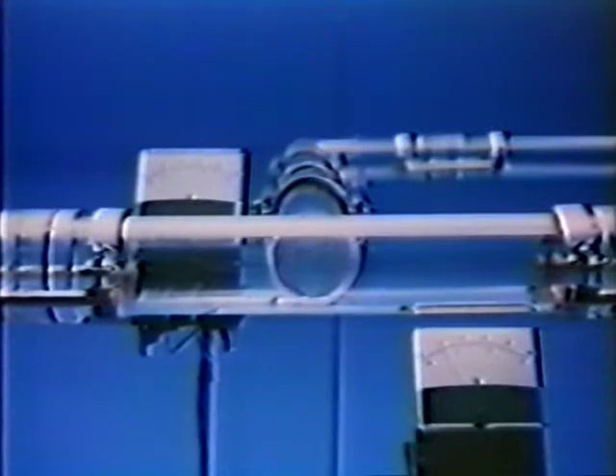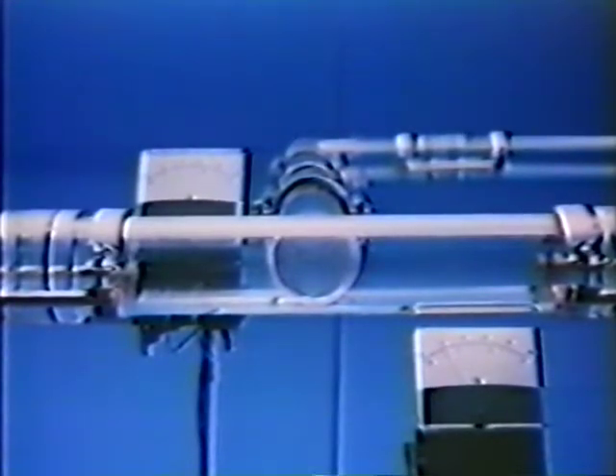The regional network, which branches out at numerous points, starts at the measuring and regulating stations. How does a flow of condensate behave at a branch point? This is the model of a pipeline with a branch line. The gas stream comes from the left. The gas flow in the branch line is measured with the meter on the left. The meter on the right measures the gas flow in the straight-through line. At this moment, the gas stream divides into two equal parts. It now appears that all of the liquid passes into the branch line.